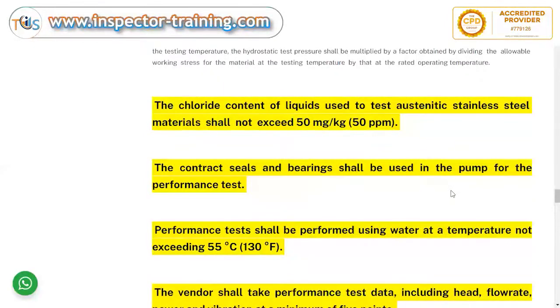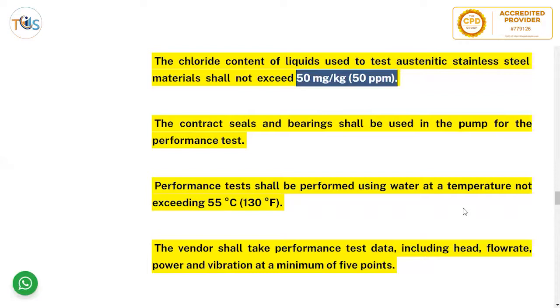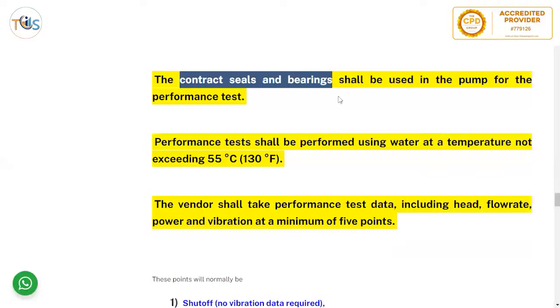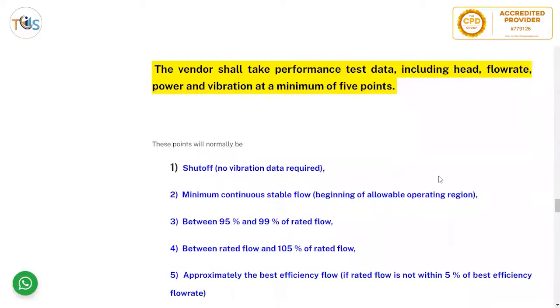The contract seals and bearings shall be used in the pump for the performance test. The performance test shall be performed using water at a temperature not exceeding 55°C (130°F). The vendor shall take performance test data including head, flow rate, power, and vibration at a minimum of five points.